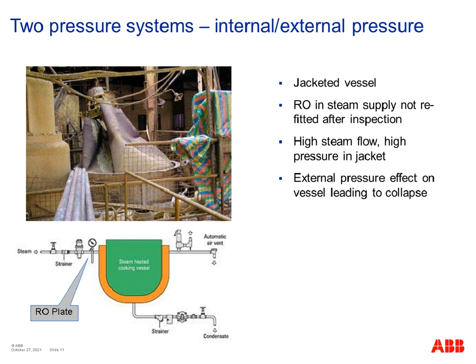So what happened here was that the RO was inspected, but it wasn't refitted after the inspection, and the equipment was brought back into service. Because there was no restriction orifice in place, as there would normally have been, there was a much higher steam flow into the jacket, and the relief valve had been designed assuming that RO was always going to be in place. So that relief valve was now undersized for the amount of steam flow coming in. It opened to try and relieve the pressure that was rising because of all this steam flow coming in and unable to leave anywhere else. But because the RO plate wasn't there, the relief valve wasn't big enough to deal with that flow. So the pressure continued to rise in the jacket.